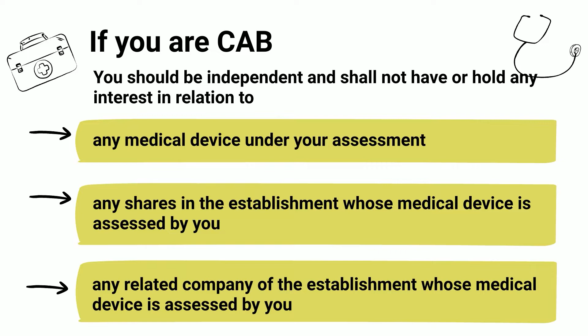Under Section 10 of Act 737, CAB should be registered with the authority to carry out conformity assessment of a medical device. The person who is in charge of a CAB shall be a Malaysian citizen. If you are a CAB, you should be independent and shall not have or hold any interest in relation to any medical device under your assessment, any shares in the establishment whose medical device is assessed by you, and any related company of the establishment whose medical device is assessed by you.